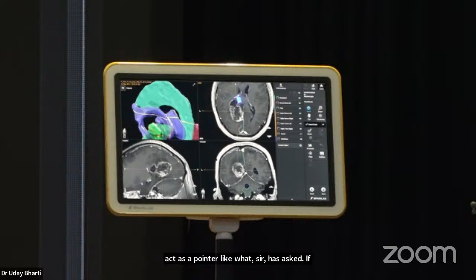But the idea behind integrating the microscope is heads-up display, which will come to your ocular, and the focus of microscope, that focus will act as a pointer tip. You don't have to bring the pointer in or the suction to see where exactly you are focusing. But yes, if you want to actually see, then you can bring in the pointer or the suction. You can calibrate third-party instruments, be it a suction or any rigid instruments, and then you can use it. It will act as a pointer. So with the microscope, you do X and Y correction, but for depth, with every depth you have to do it. So it's a process that is time consuming.